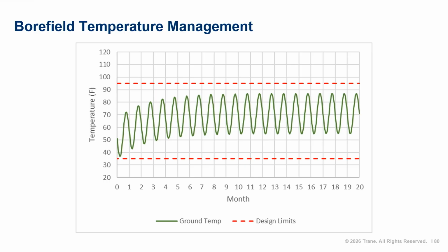Long-term management of ground temperature is a slow process entailing small adjustments to the system operation from one year to the next. A skilled operator might make these tweaks intuitively. System controllers can be configured to adjust system operation based on the year-over-year temperature drift. And looking ahead, AI software packages will be used to optimize HVAC system operation in real time, including ground loop temperature management.